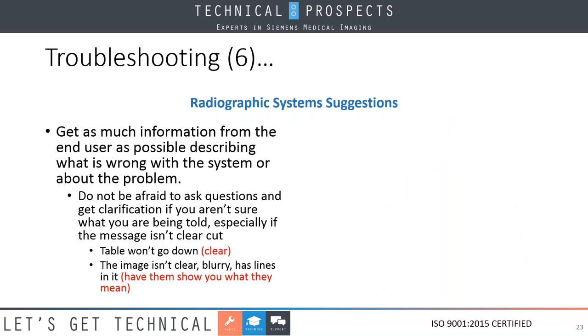All right. So here's some suggestions about troubleshooting radiographic systems. Get as much information from the end user as possible. The biggest thing is don't be afraid to ask questions, especially if their message isn't clear cut. Do not assume, and this is one of the biggest things that I find about field engineers, and I was guilty of it in my early days as well. For example, table won't go down. That's a pretty clear symptom. However, when an operator says, this image isn't clear, it's blurry, it has lines in it, show me. Don't be afraid to say that. Get an understanding of what they're looking for. Let them give you their level of expertise, because then you can apply it to the machine.